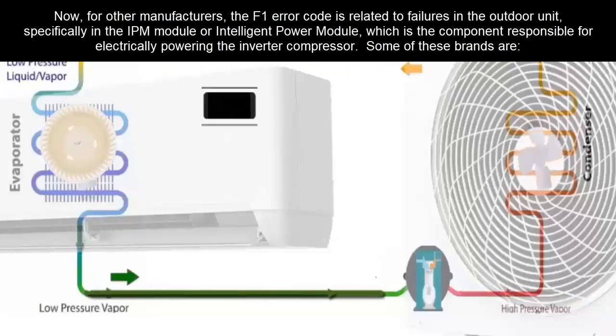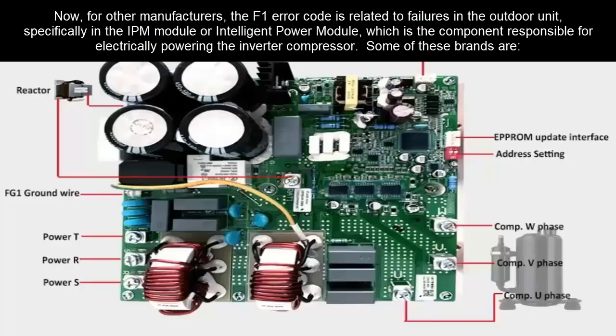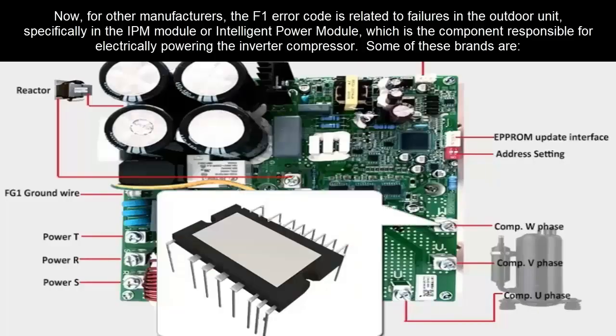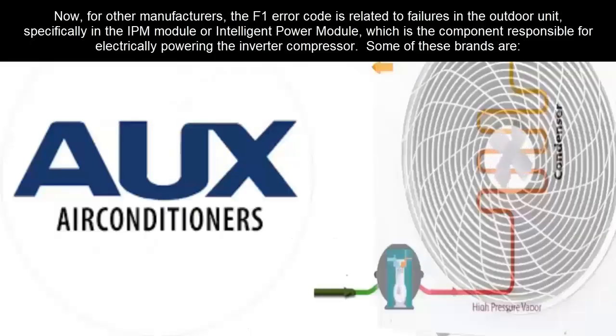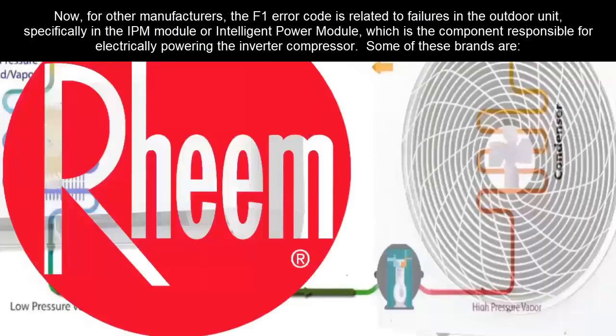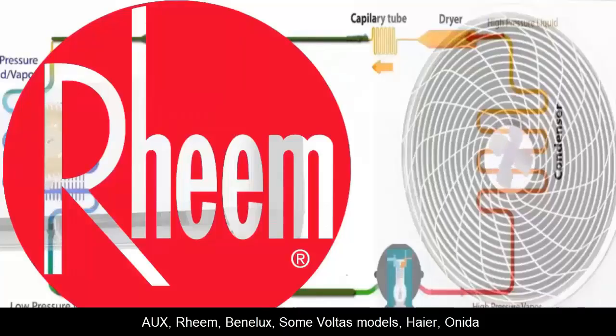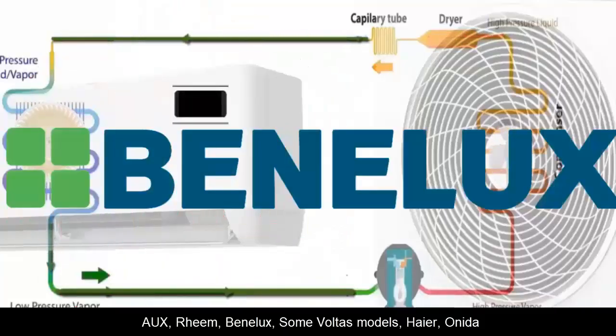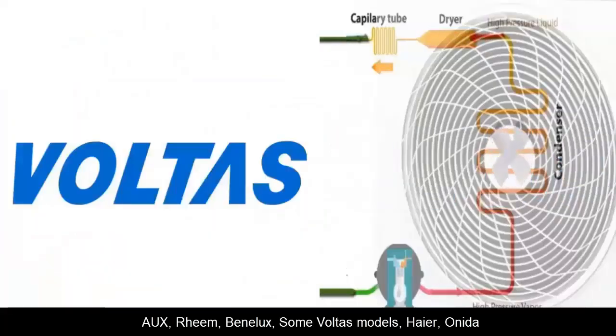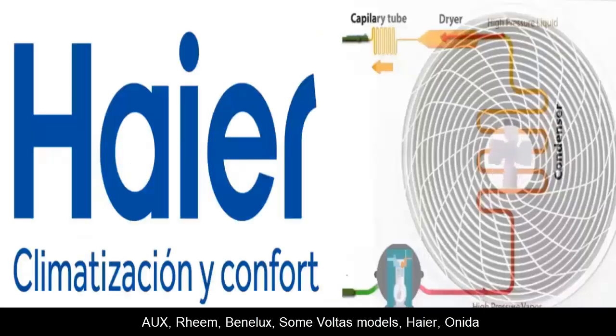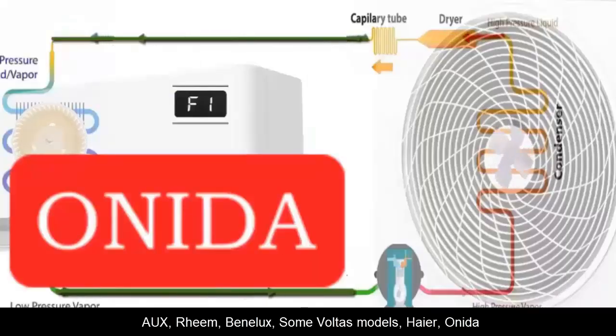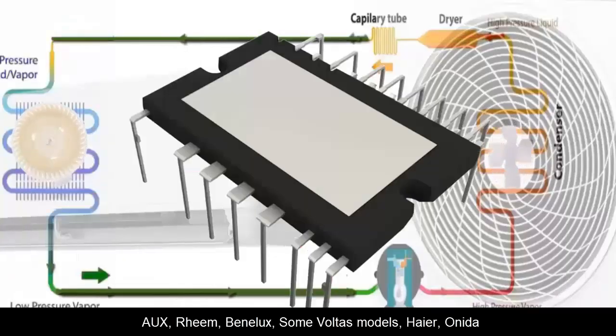Now, for other manufacturers, the F1 error code is related to failures in the outdoor unit, specifically in the IPM module or Intelligent Power Module, which is the component responsible for electrically powering the inverter compressor. Some of these brands are AUX, Rheem, Benelux. Some Voltas models: Haier, Onida.